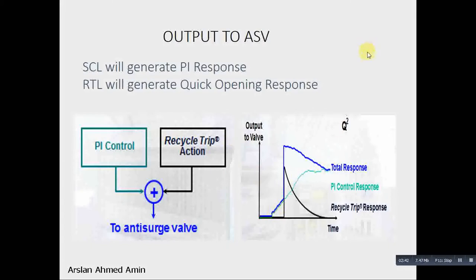One may question, why not a PID controller is used? So the answer to this question is, in a PID controller, the derivative action would be concerned both for opening and closing of the valve. Since this is a flow application, a flow application will normally not use the derivative action because it causes noise in the control loop.